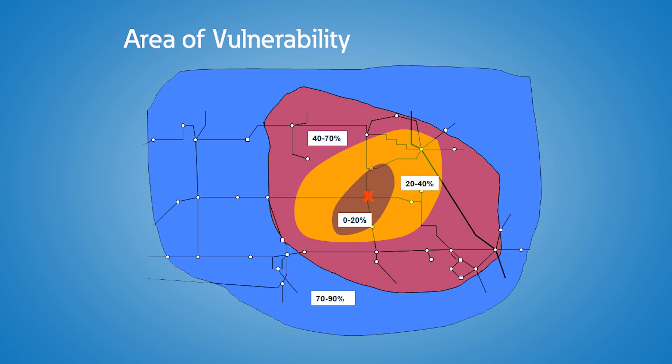Typically, when the utility distribution has a fault, the voltage at the location of the fault is zero. But because the electrical power grid is interconnected with many generation sources, the voltage at a location remote to the fault is greater than zero. Generally speaking, the farther away you are from the fault, the higher your retained voltage will be.